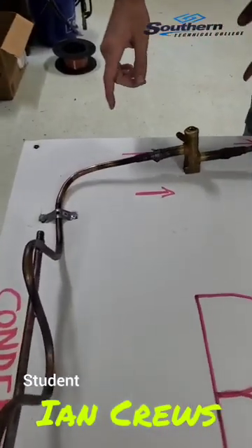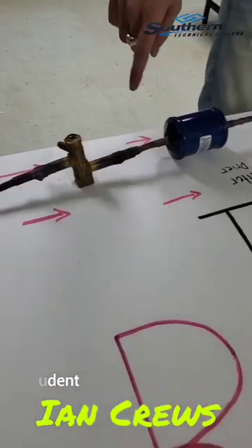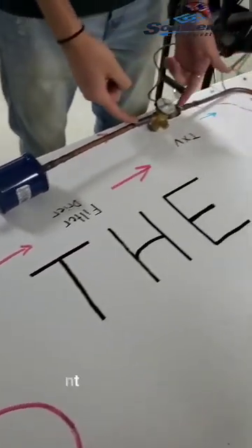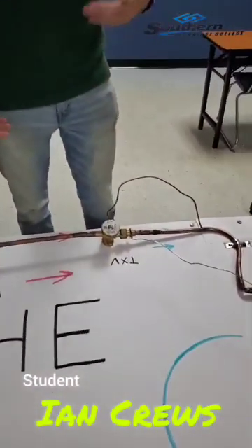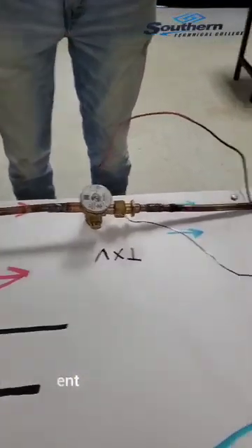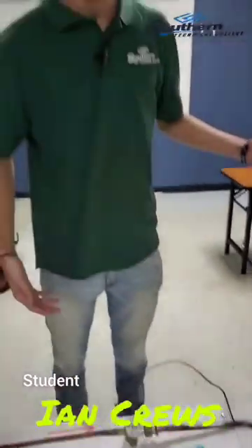Thank you, Jaffet. So as the liquid refrigerant makes its way through the filter dryer, it comes to the TXV, which is a metering device. A metering device causes a pressure drop that in turn causes a phenomenon called flash gas, where the refrigerant flashes off to about 75% liquid and about 25% vapor.